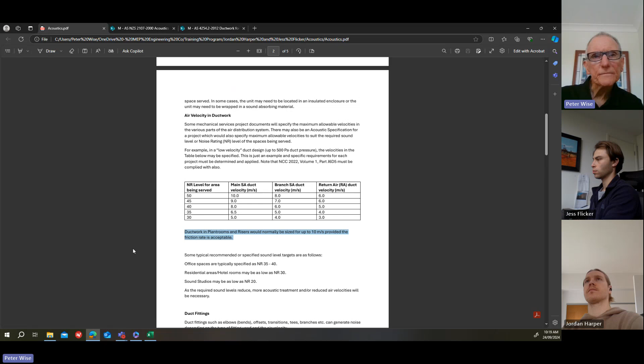And I put down a few typical recommended sound levels there. Office spaces are typically NR35 to NR40, which in dBA, if you're looking at AS2107, it'll say 40 to 45. Residential areas, 35 to 40 dBA, depending on the bedroom, would be different. Obviously, if you're going to run air conditioning at night, it needs to be quiet. So for a bedroom in a residential building, you might be trying to achieve 30 to 35 dBA like that meeting room. And sound studios can be quite low.